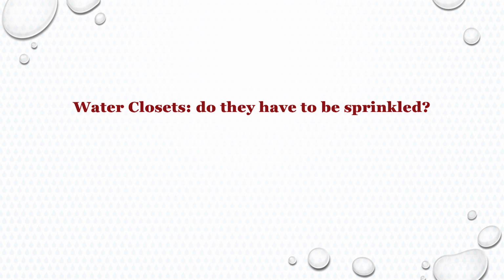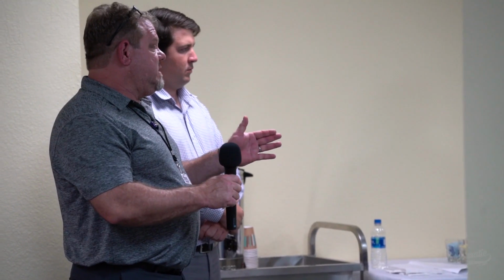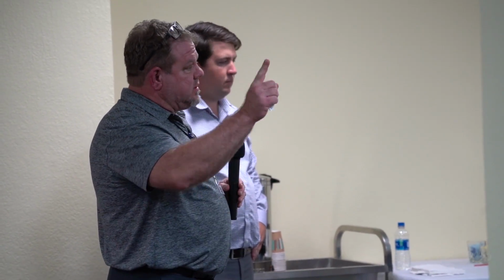Water closets were mentioned, do they also have to be sprinkled? Not inside the unit, only the HVAC closets, the common ones. Sometimes you'll have an HVAC closet that opens to the corridor - those would be required to be sprinkled. Anything inside doesn't have to be sprinkled. So in our case, where we have 2 apartment doors plus the HVAC closet, we need 3 sprinklers for each unit, plus the corridor.